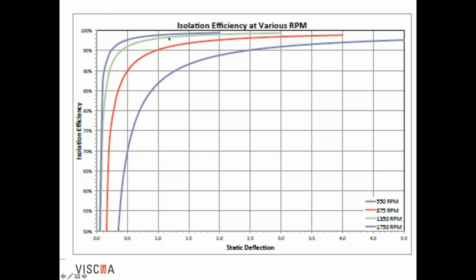So anything plus or minus a good 25% within this range where it would be selected, I'm not going to see a change in my isolation efficiency. So don't be worried that you're not getting a 1-inch deflection from a 1-inch deflection spring. Springs can only be made by wire diameter and heights and all the other geometry, so I can't have an infinite variety or an infinitely variable spring. I have a spring that's 800 pounds per inch, 1,000 pounds per inch, 1,200 pounds per inch, whatever it may be. So you have incremental selections. So you can never hit that 1%.